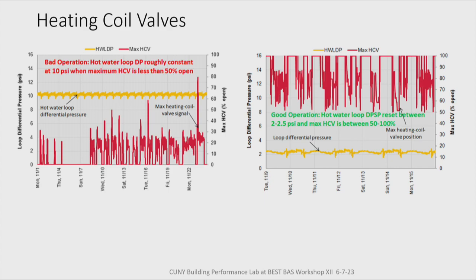Any comments? Unlike the previous damper example, this is only showing one valve, not the whole population of valves. Typically, when doing this kind of analysis with loop differential pressure, we look across the whole population of valves to make sure we satisfy the worst case. That worst case may indicate a balance condition or a rogue zone, so we want to pay attention to that. But in general, the principle is to reduce the loop pressure by looking at your operating components and seeing if they're highly throttled.